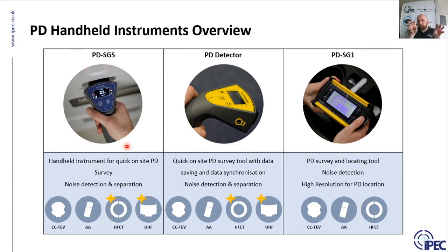The resolution between these two sensors is 240 picoseconds, which is the equivalent of about 8 centimeters at the speed of light. So these TEV signals can be accurately located to about 8 centimeters, which is the most accurate location device available.